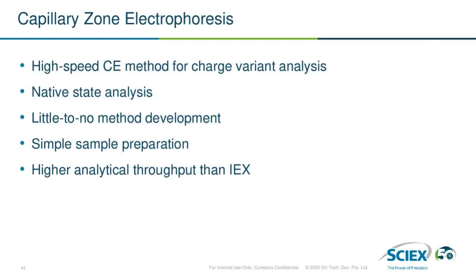Rapid charge analysis by this application can resolve a native state molecule's charge variations with little to no method development and provide higher resolution than imaged capillary isoelectric focusing or anion exchange chromatography. The separation is based on charge to hydrodynamic ratio. This method provides a fast, powerful separation used to quantify charge variants with a buffer that serves as both separation matrix and dynamic coating for a bare fused silica capillary.